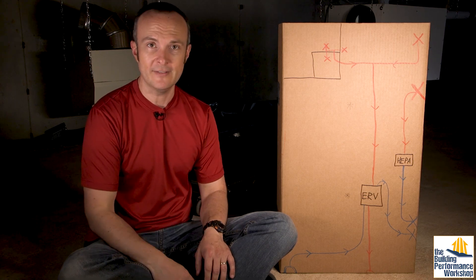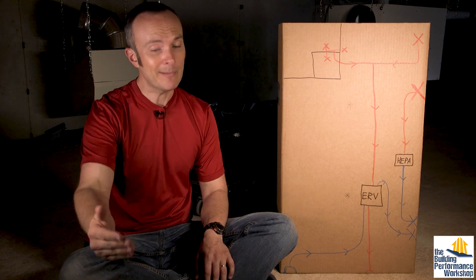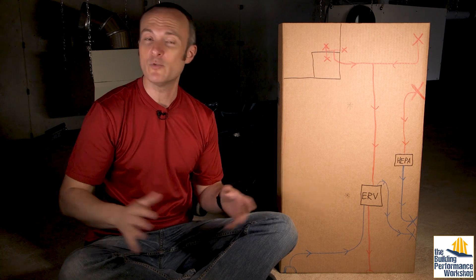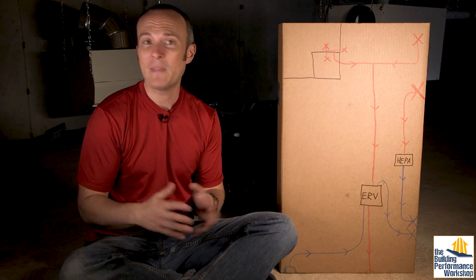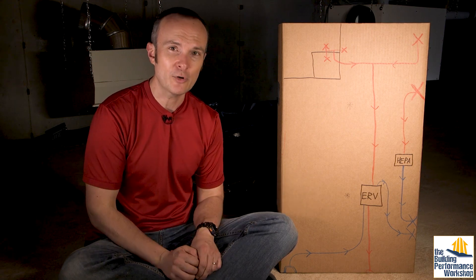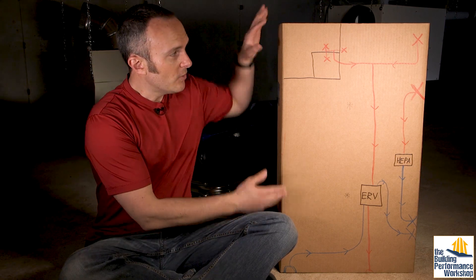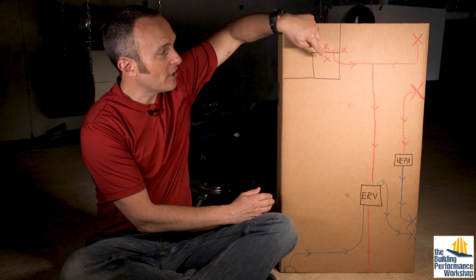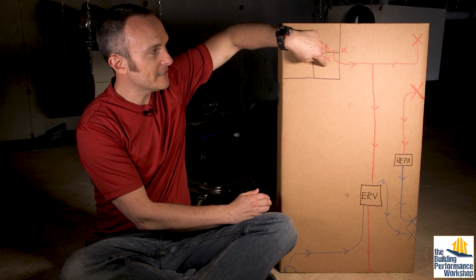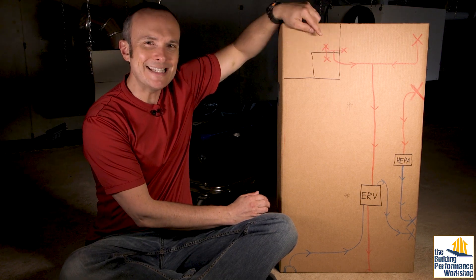So what we've done with these two pieces of ventilation equipment is something kind of interesting and unique, and I just wanted to show it to you because it's very easy to understand. Over here on my left is a Fantech ERV — that stands for Energy Recovery Ventilator. This is a machine that has two duct collars you can see here and two on the other side. It's going to take stale air from the space above us and take that to outside, and bring outdoor air in and deliver it into the space in equal measure so that it's pressure balanced.